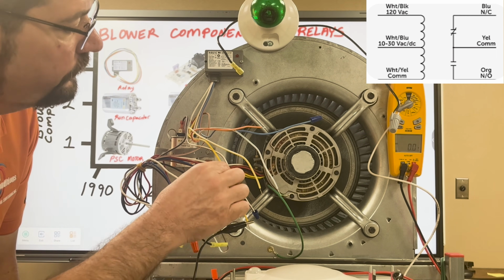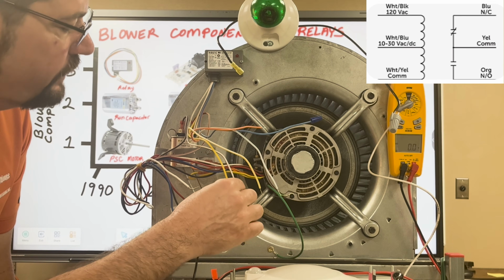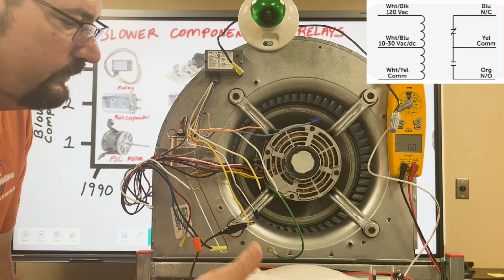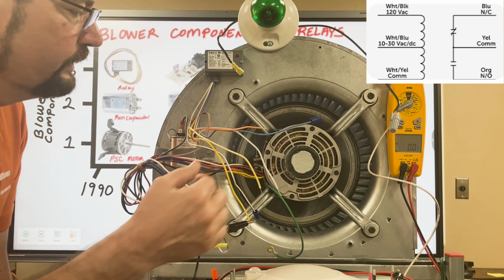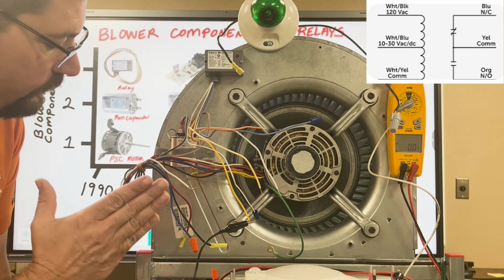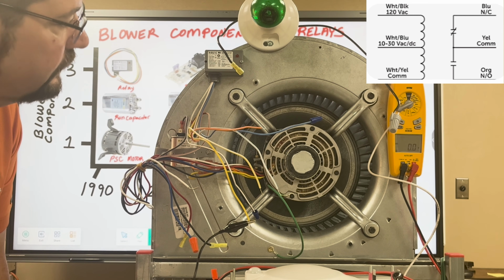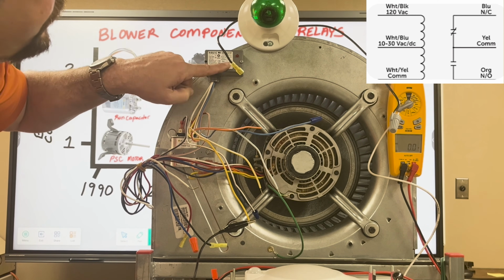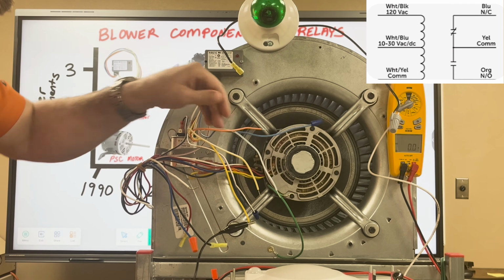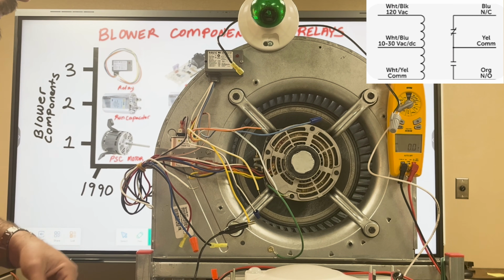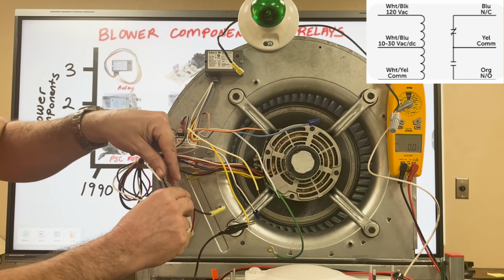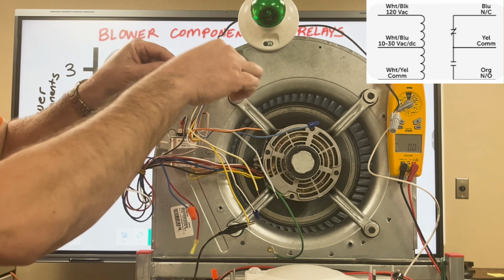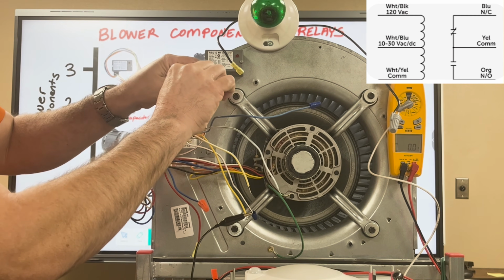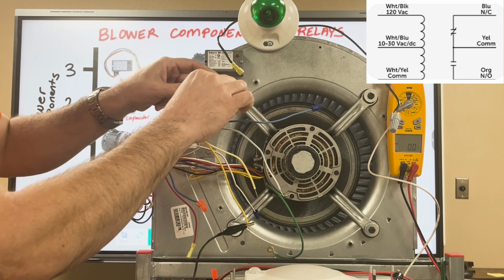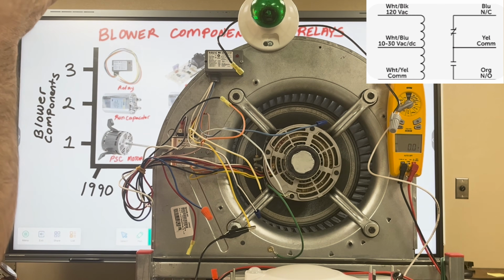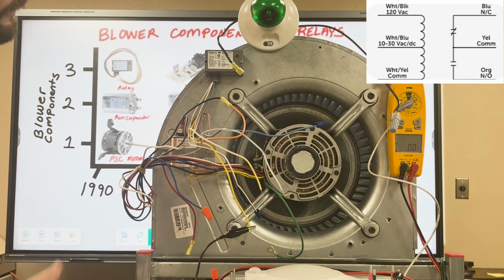So we have one solid color wired up, which is yellow. That's line voltage coming in as an input, and that's the only thing that's wired up right now. So we want to take orange, which is normally open, and wire that to one side of our fan motor. We're going to pick black, which is high speed. I'm just going to push this inside of it. That should make a good enough connection there. Okay, and that's for the fan motor.